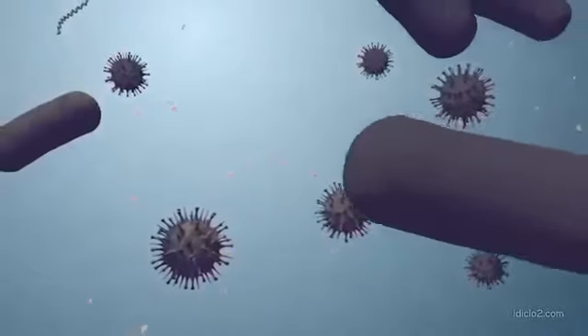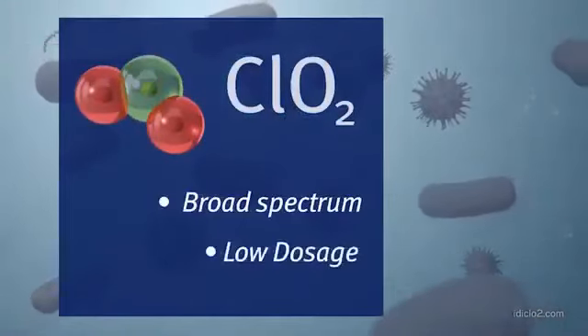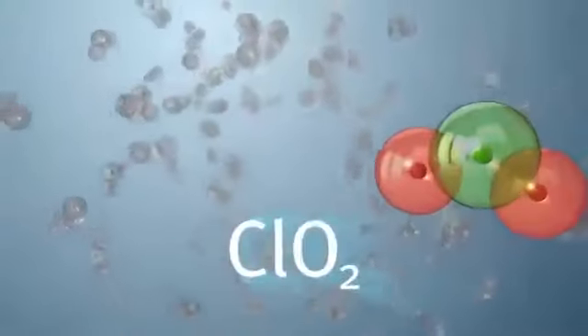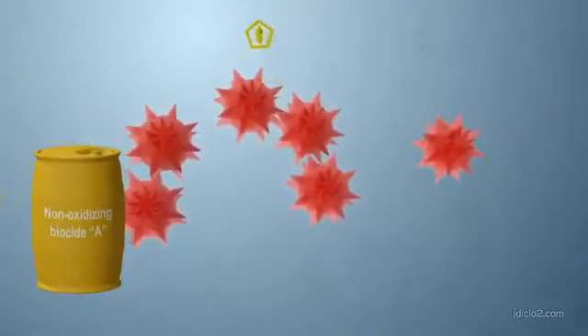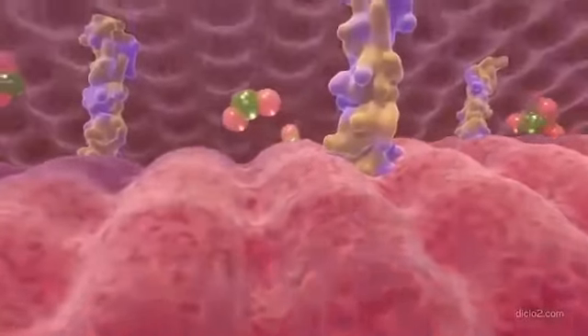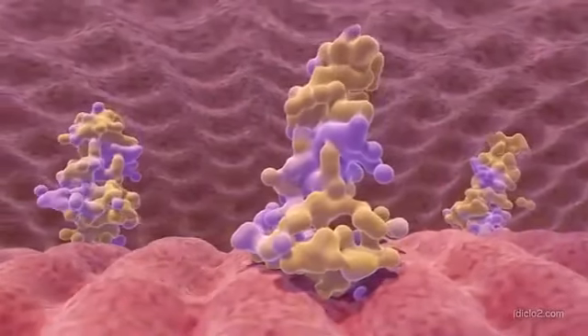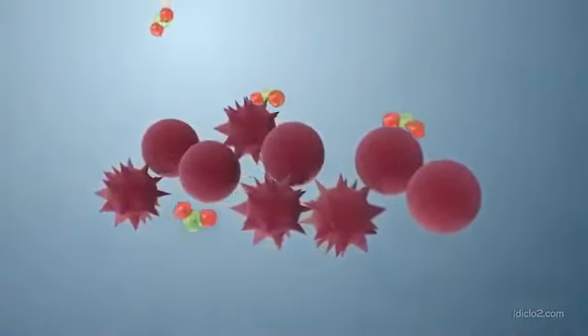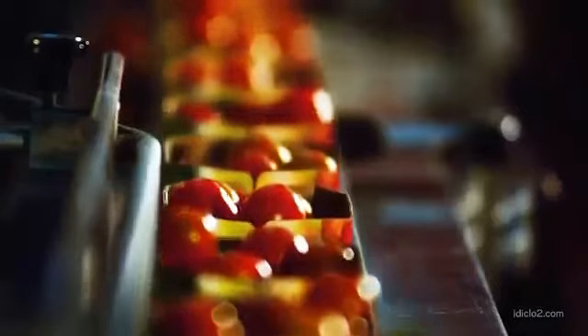The collective damage from this multifaceted attack prevents the microorganism from developing resistance and makes ClO2 both broad-spectrum and efficacious at a low dose. Chlorine dioxide is a fast-acting, highly effective oxidizing biocide. Microorganisms are known to alter their structure to develop immunity to non-oxidizing microbicides. The typical solution to this problem is to alternate non-oxidizing biocidal chemistries. ClO2 rapidly diffuses through cell membranes, oxidizing critical proteins and amino acids inside of the microorganism. These reactions disable cell metabolism and prevent microorganisms from developing a resistance mechanism. The use of chlorine dioxide eliminates the need to alternate biocidal chemistries in critical applications like food sanitation and drinking water disinfection.